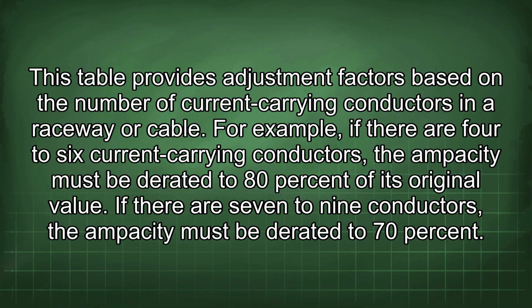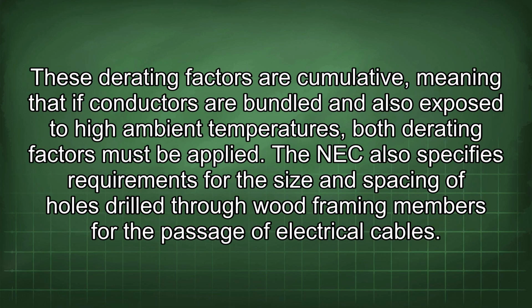For example, if there are 4 to 6 current-carrying conductors, the ampacity must be derated to 80% of its original value. If there are 7 to 9 conductors, the ampacity must be derated to 70%. These derating factors are cumulative, meaning that if conductors are bundled and also exposed to high ambient temperatures, both derating factors must be applied. The NEC also specifies requirements for the size and spacing of holes drilled through wood framing members for the passage of electrical cables.